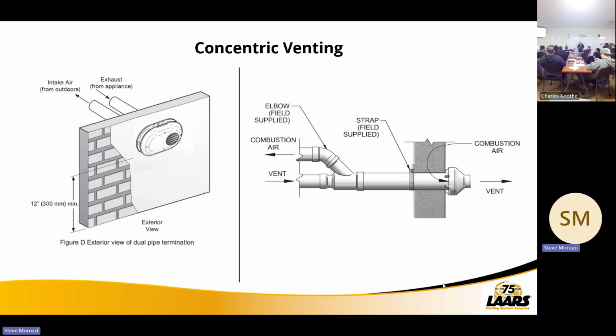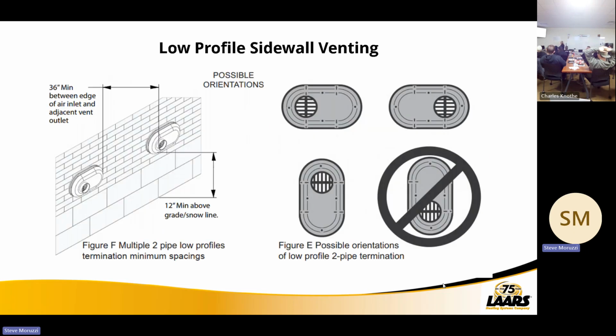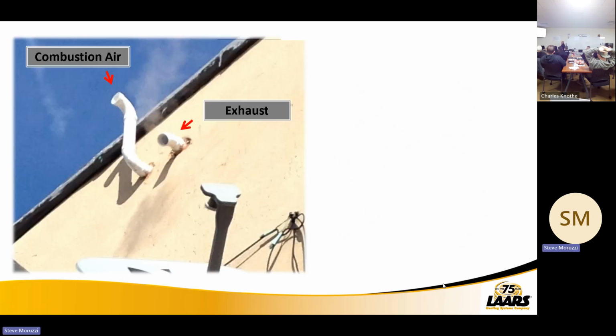So again, concentric, we are certified for the flush mount kit or the bazooka type. In the right-hand image, I had asked somebody earlier about how far is that supposed to be off the dwelling, and someone told me 12 inches. Well, if you read those instructions, they're supposed to be touching, as shown here. Okay? There's a little tab on those collars that keeps you off about 1 inch. All right, so make sure you follow those instructions and how they should be installed, distance between them as well.